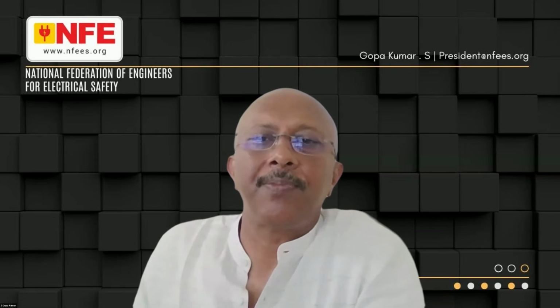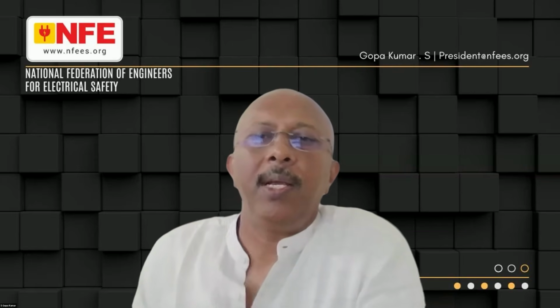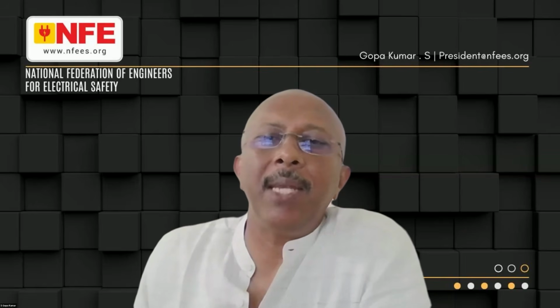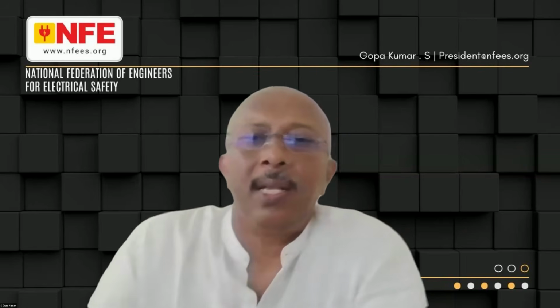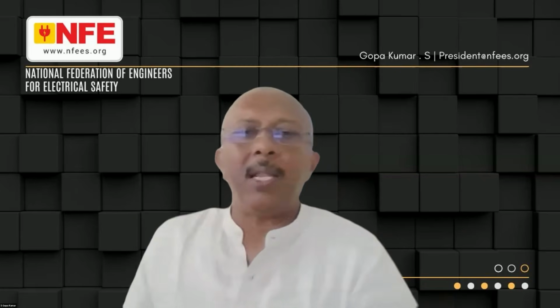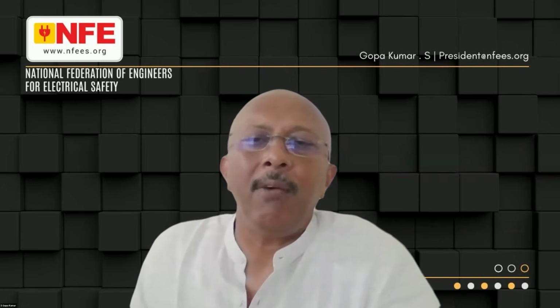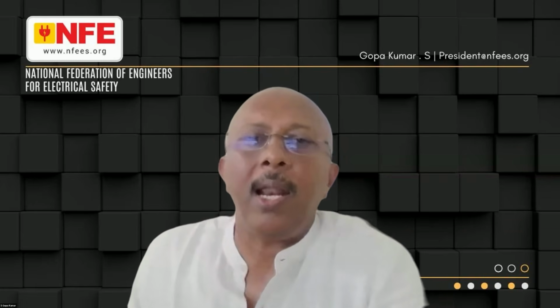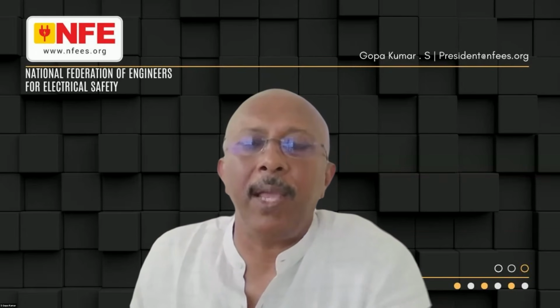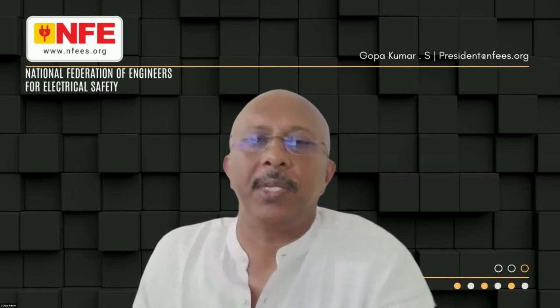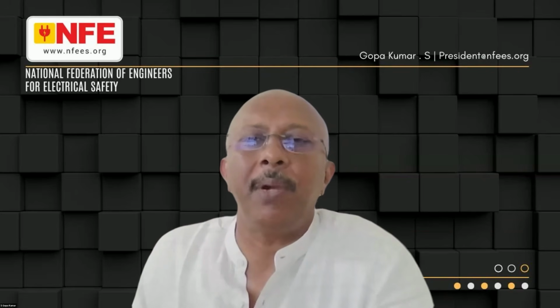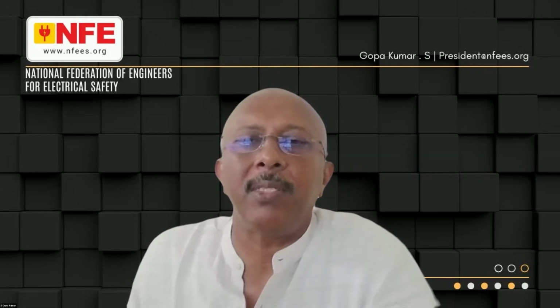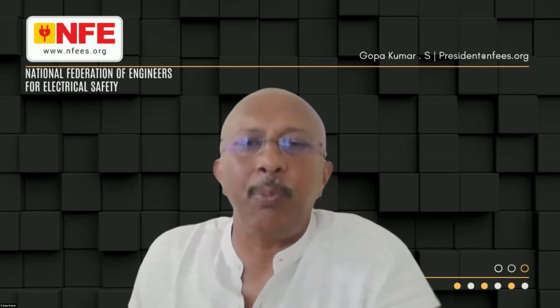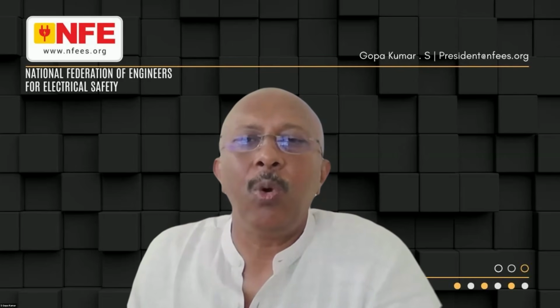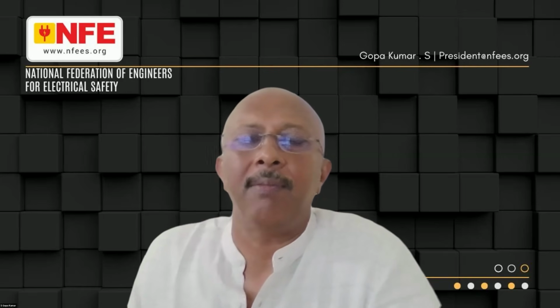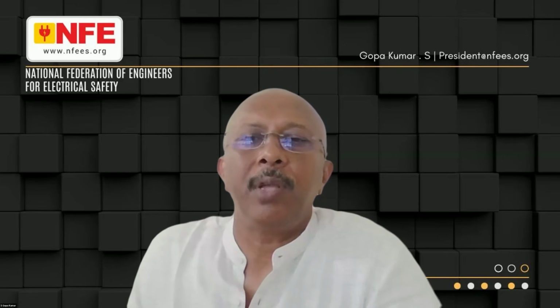The next question is from Neeraj Kumar Maurya. For a UPS system, a dedicated earth pit is required as demanded by the OEM. Mr. Neeraj, the OEMs are demanding a separate earth pit mostly because they are unaware of what they are selling. They are unaware of their own equipment. Better you find a good quality UPS supplier who knows the subject. That is the only recommendation I can give. If any of these electrical or electronic equipment manufacturers are demanding a separate earth pit, be very clear that they don't know the subject. It is better to change your vendor.